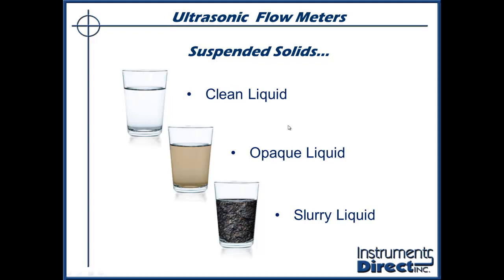Let's talk more about suspended solids. Here's clean water — ultrasonic Dopplers do not work in clean water unless heavily aerated, and unless you have zero pressure in your line, it never will be heavily aerated. Once you get more than a couple pounds of pressure, aeration goes to the top of the pipe or just doesn't work. Opaque liquids are a colored liquid with dissolved solids. People call and say they have dissolved solids, but dissolved solids don't matter for Doppler flow meters. If your cup of tea has no tea flakes — only dissolved solids — a Doppler flow meter will not work on that.